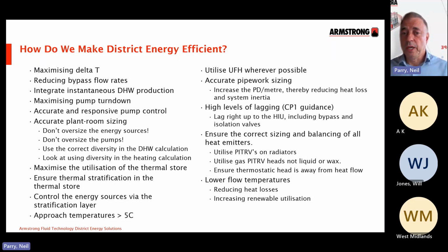We need to look from the pump's point of view at how we maximize that pump turn down. We need a really big delta between peak demand and low demand. Maximize that as much as possible. And with today's pumps, we can typically get down to 5 to 8% of peak load without too many issues at all. Accurate plant room sizing, so don't oversize the energy sources. There's often a tendency to say, well, I don't want to cut things too tight, so I'm going to add a bit of extra in here and then a bit of extra over there, and these things start to add up as you go through the sizing calculations, and they tend to compound each other, and we end up significantly oversizing things. Particularly bad from a pump point of view as well, because by having a much larger pump, you find that it can't turn down far enough, and you've got a much smaller operating delta between the peak flow and an idle flow, if you like.